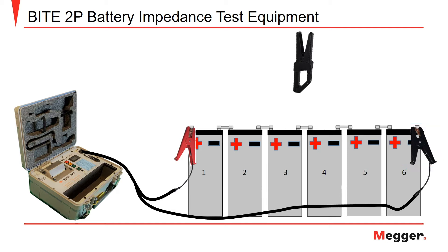Following this, you will need to connect the amp clamp around one of the intercell battery straps of the string. In this case, you will be connecting it around the strap between cells three and four. The amp clamp will remain in place for the duration of the test procedure.